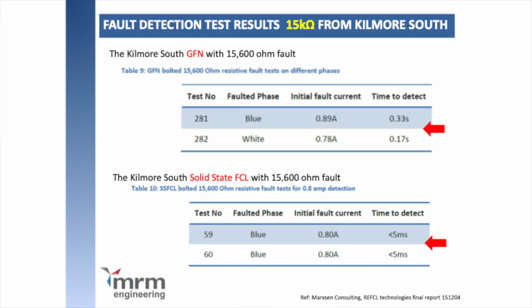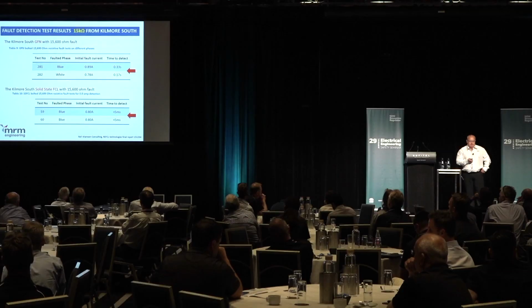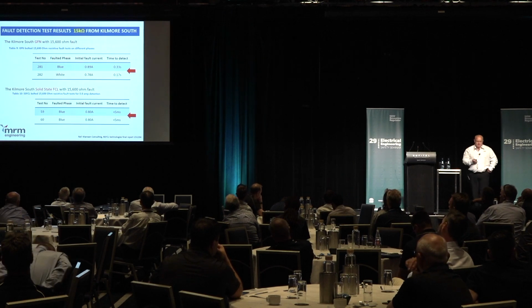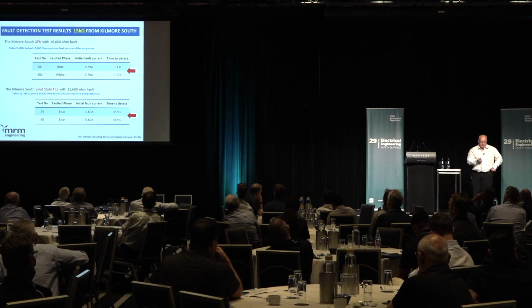So with the 15 k ohm, this is where they set a medium level ground impedance. The time to detect was down at 0.33 on one test and 0.17. And then the solid state RFCL cleared in less than 5 milliseconds. So their protection now on this line, depending on which way they go, is going to clear somewhere less than 5 milliseconds for a solid state, or they're going to be down at 0.33 seconds for a ground fault neutraliser.